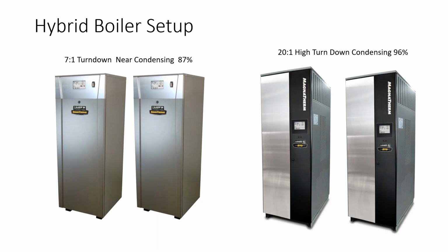But here's the key that you're probably not thinking. Near condensing products are only about 30% more than a standard efficiency boiler, or 85% mid-efficiency boiler, with all the advanced controls. The Magnatherms, or the high efficiency condensing boilers, are double that price or triple in some cases, depending upon what you're using. So by doing this, you're getting a design that's built for the application, being able to handle condensing, even if the design of the system is to always use the Magnatherms. What a hybrid boiler plant would do, would say, okay, our outdoor temperature is way too cold, and our return temperatures are way too high for condensing. Let me switch the primary over to the near condensing product and let that be the primary secondary boiler, and have the third and fourth boiler be the condensing boilers.